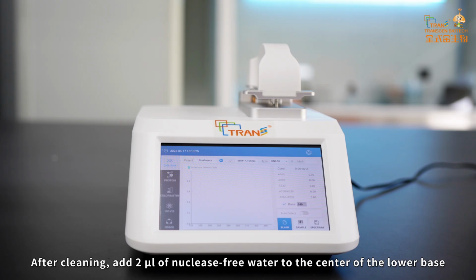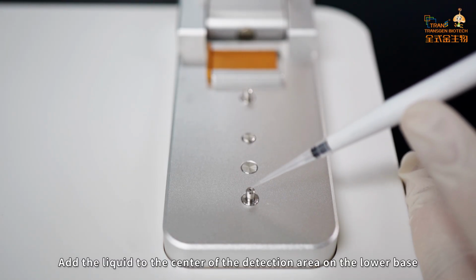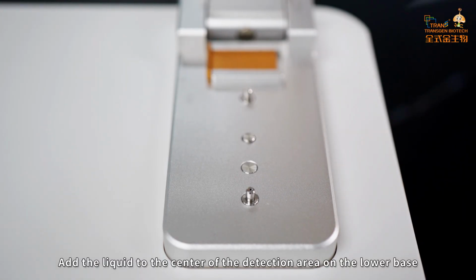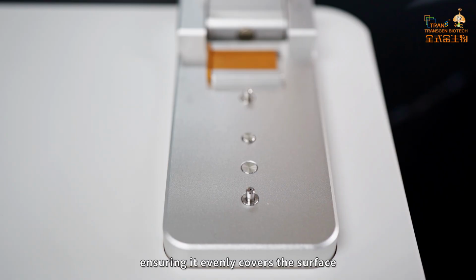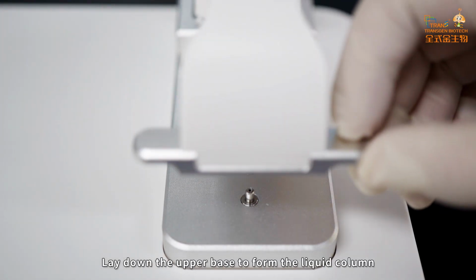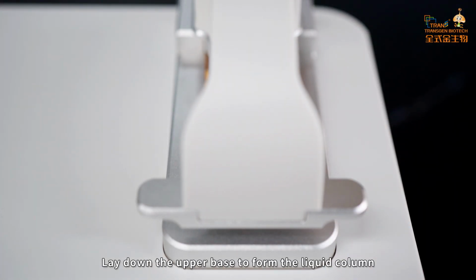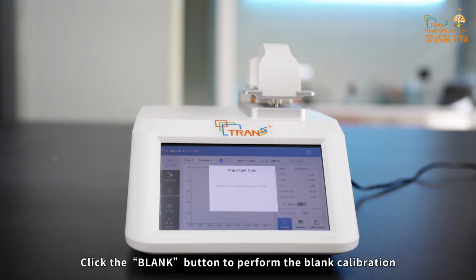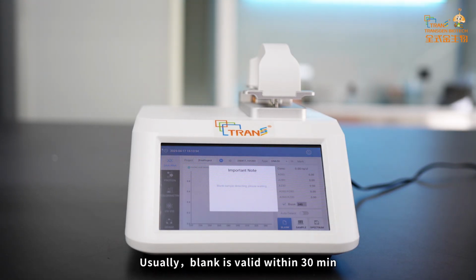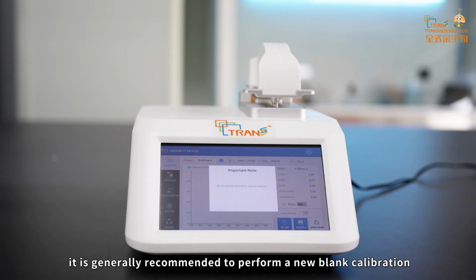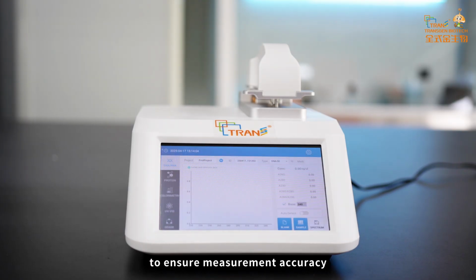After cleaning, add 2 µl of nuclease-free water to the center of the lower base. Add the liquid to the center of the detection area on the lower base, ensuring it evenly covers the surface. Lay down the upper base to form the liquid column. Click the blank button to perform the blank calibration. Usually, blank is valid within 30 minutes. After 30 minutes, it's generally recommended to perform a new blank calibration to ensure measurement accuracy.